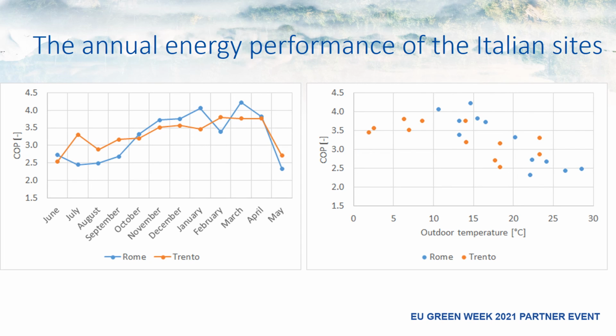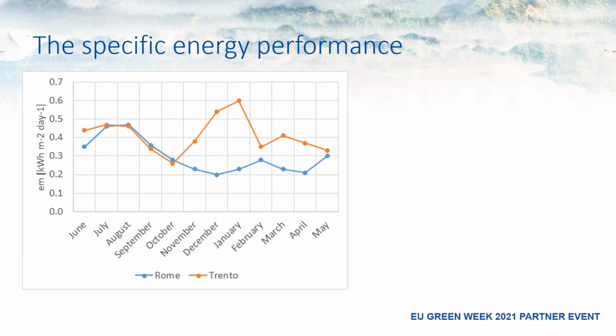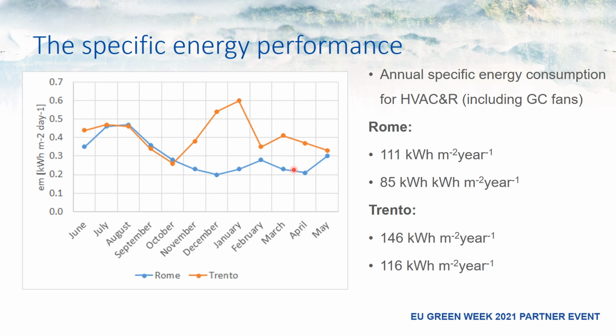Finally, we have merged the data of the two sites to show you the COP of the two systems month by month, and then we have plotted the same values here as a function of the outdoor temperature. We have also selected as a key performance indicator the specific energy consumption. This is the specific energy consumption, so kilowatt-hour per square meter per day, average value for each month for both sites. Trento is always orange and Rome is always blue. And the global values, so kilowatt-hour per square meter per year, for the Rome and the Trento site.